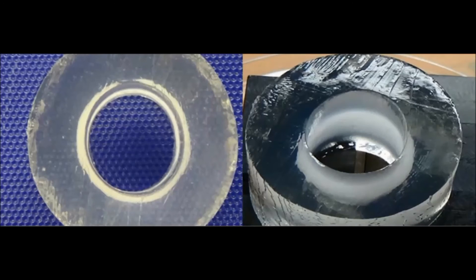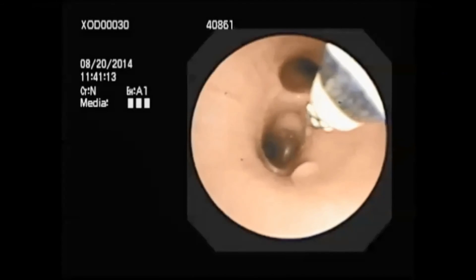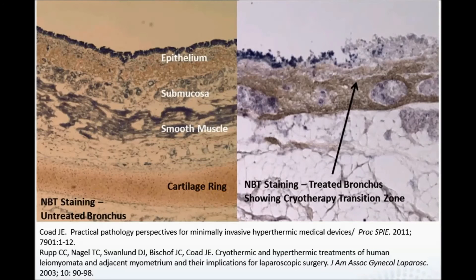This figure shows test results performed on an 18mm lumen for one hole pattern configuration, demonstrating the feasibility of uniform circumferential spray. This sample generated uniform circumferential freeze zones in various quadrants in all relevant lumen diameters. A porcine luminal model was used as the in vivo model to test various hole patterns. An example of a metered cryospray in a segmental lumen is shown in this video with a complete circumferential cryofrost. Viability staining that identifies cryoablated intact dead cells in recently treated extirpated animal tissue was used to establish the correlation of gel test stand measurements with animal pathology.